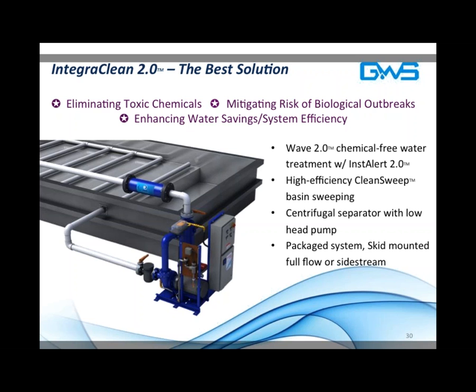If the customer wants to go full flow with the wave component, and that might be required in some unusual applications, or if you're wishing to treat a common recirculating header, for example, then of course you'd have to splice into that recirculating header, and the shutdown time corresponds to whatever it would take to cut and weld flanges in for a 4-foot section of pipe. But the short answer is that for side stream applications, there is often no shutdown required.